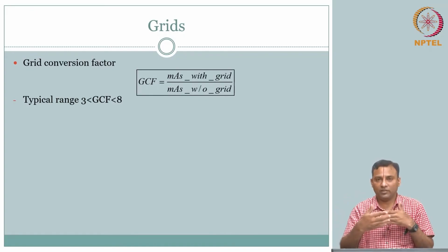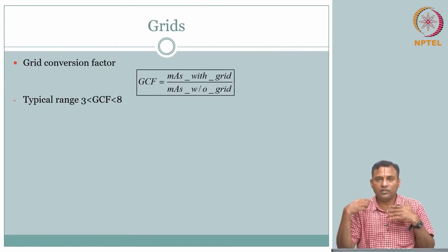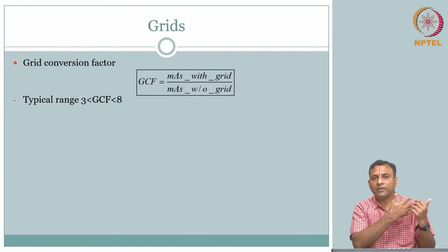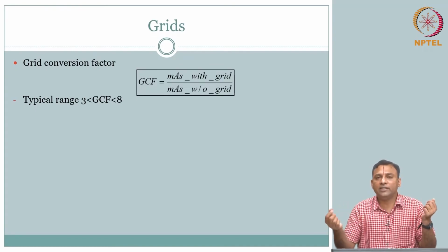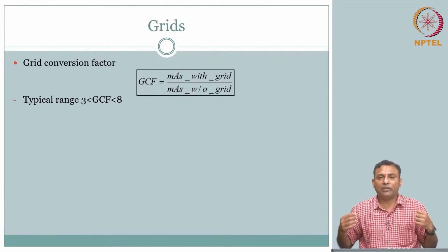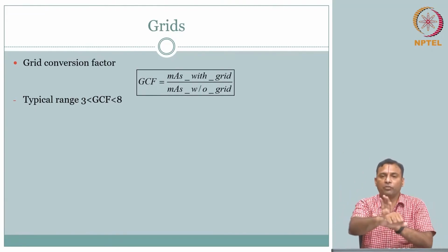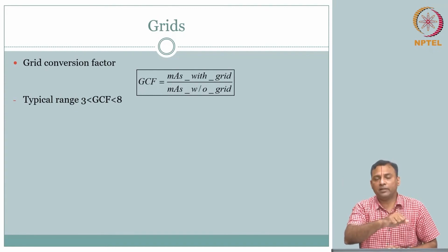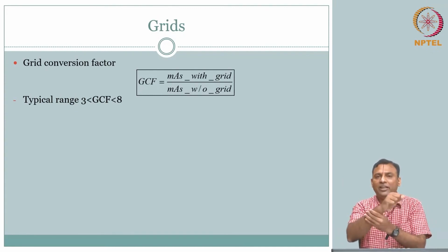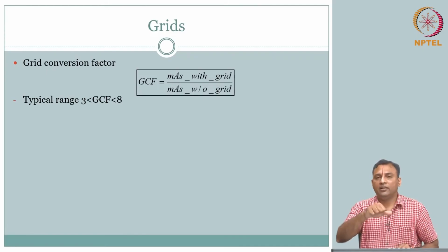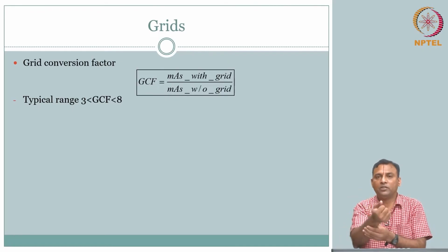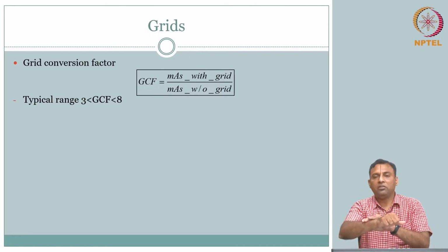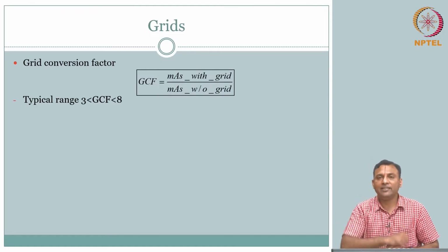So, if the thickness is more, then there is a chance of more Compton scattering coming out at angles that are going to cause problems. So, a rule of thumb that they have figured out is, if it is less than 10 centimeters thickness that we are talking about. So, if you go for your arm imaging, you break a bone or suspect that you break a bone, maybe it's not that thick, right? The depth you can place it so that it's not much thicker, 2, 3, 4 centimeters, something like that. You don't gain much.